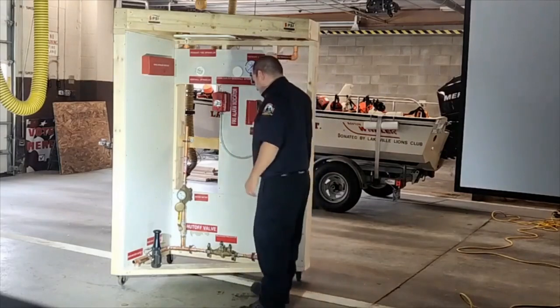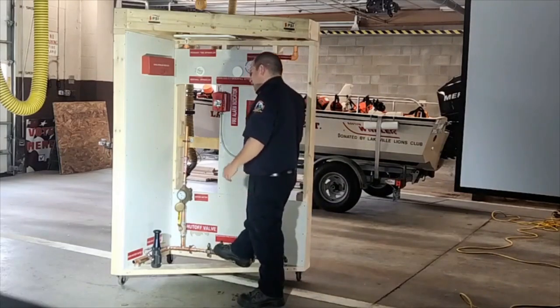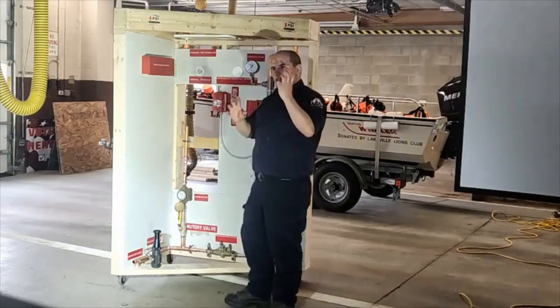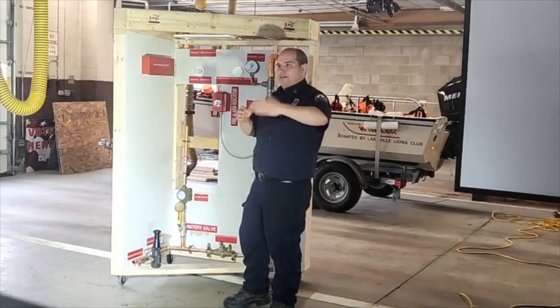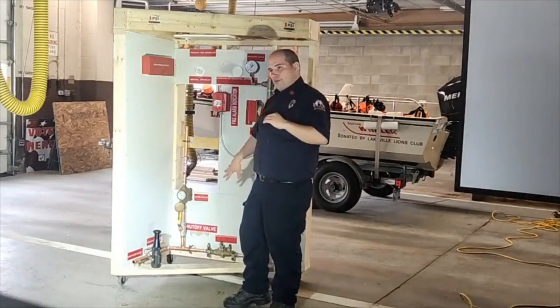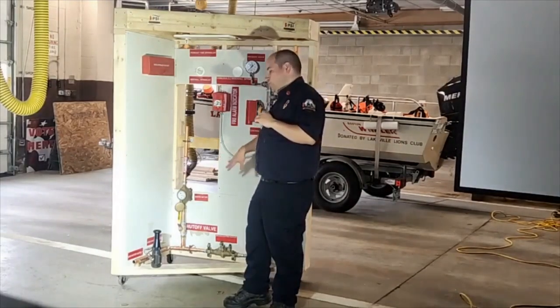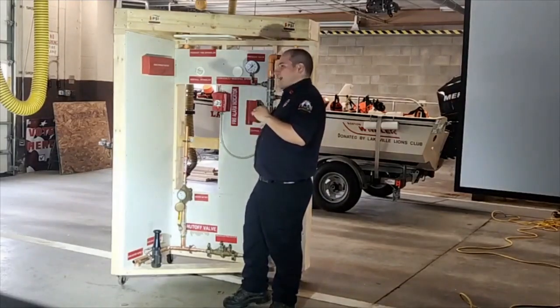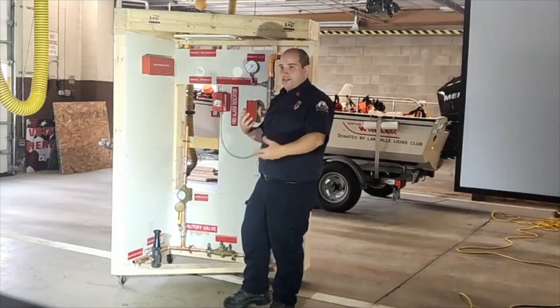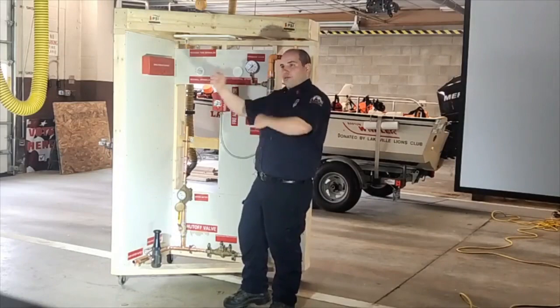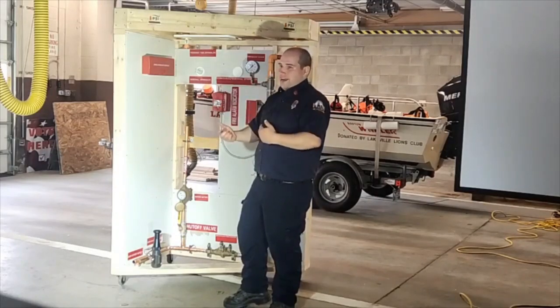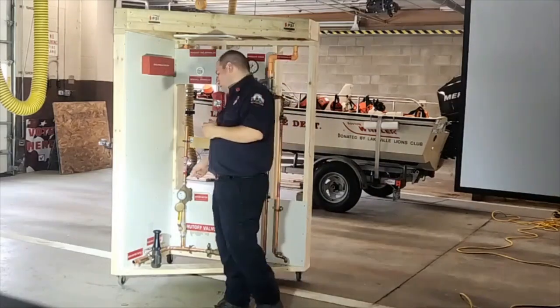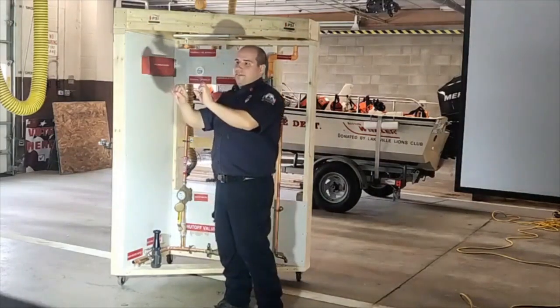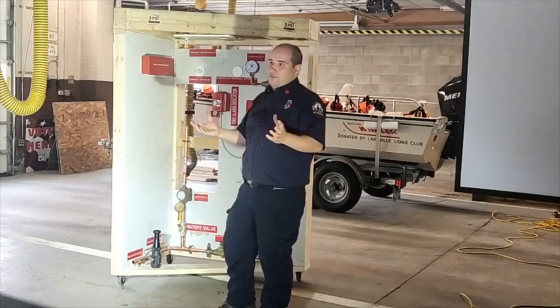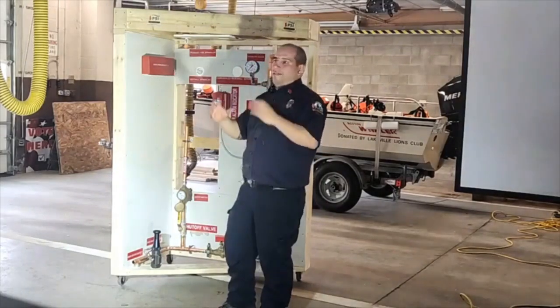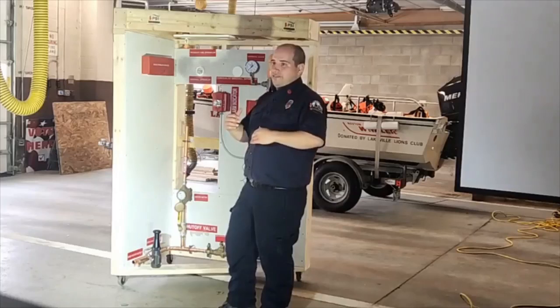They put a backflow preventer here. A lot of communities require this because the water in a sprinkler system is stagnant, and they don't want it backing up into the domestic side. That's not required per the NFPA 13D standard, and now, to eliminate the need for it, they can tie the sprinkler system into one of your toilets. When you flush, it cycles the water through the system so it's never stagnant. That's a big cost savings, because you can get rid of the backflow preventer and also reduce the size of piping needed, since you don't have to overcome that pressure. There's all kinds of new technology out there that helps drive the cost of these sprinkler systems down.